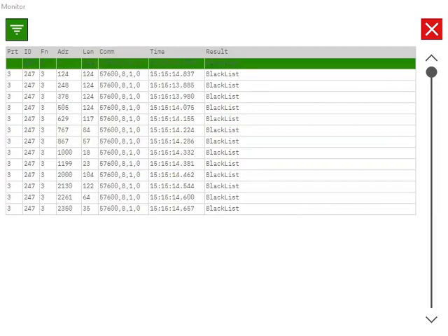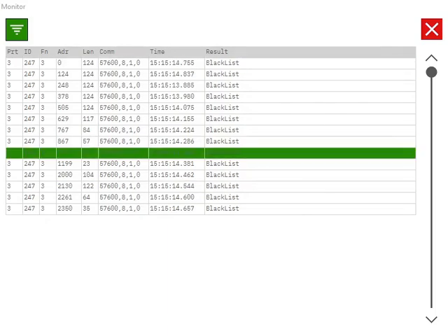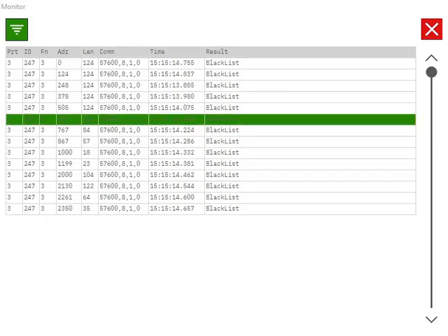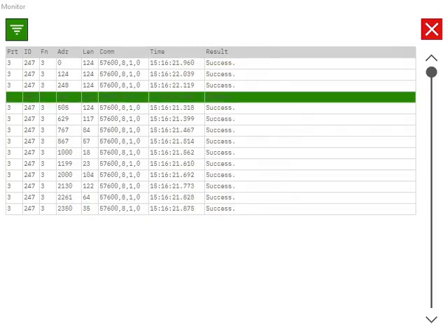Blacklist mode ensures that multiple devices wired to a single port do not have their data delayed. As you can see, an NXF4000 has 14 messages, so attempts to process and waiting for timeout for all of these will cause delays. As soon as the first message is successfully read, the device moves out of blacklist mode and the remaining messages can be processed.